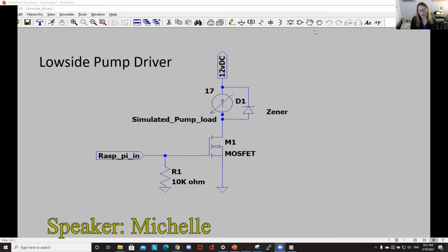How we're going to do this is we're going to write a Python script. That script will read two I2C K-type thermocouple amplifiers and compare those temperatures to the optimal range we want our working fluid to reach for max output. So if it's not within the range we need, we're going to vary the pump by adjusting the gate inputs to either slow the fluid down or increase it.